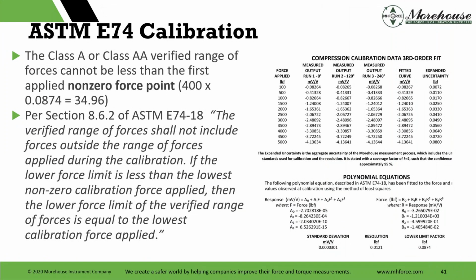So more about E74. The Class A or Class AA verified range of forces cannot be less than the first applied non-zero force point. As I said earlier, that means we're 100. And this, see, I was saying 33. My math was bad. It's 34.96. So 400 times 0.0874 equals 34.96. Theoretically, the customer could have used this cell. If our first force point would have been 34 pounds, they could have used it from 34.96 to 5,000. We chose to do the 2%.